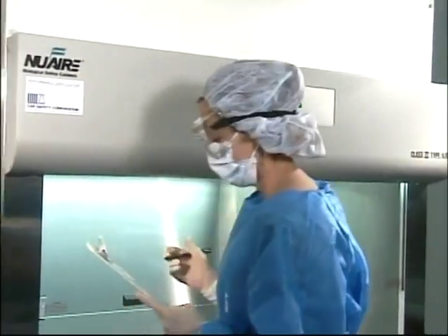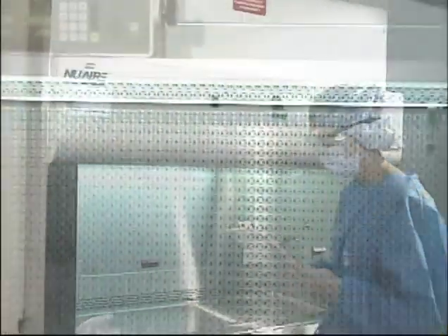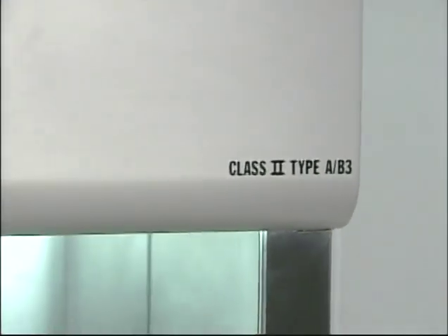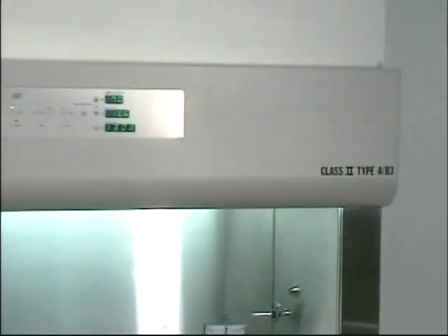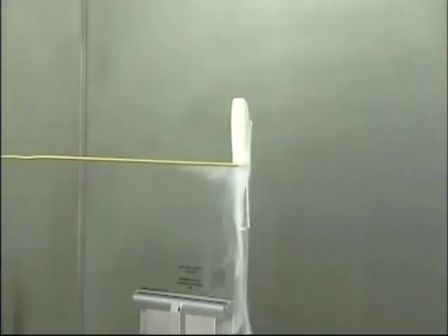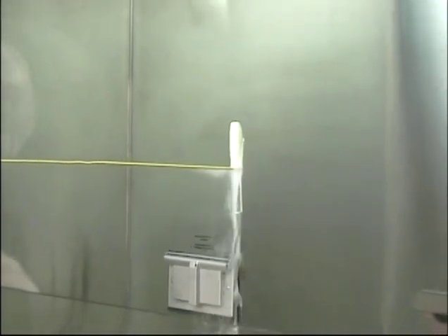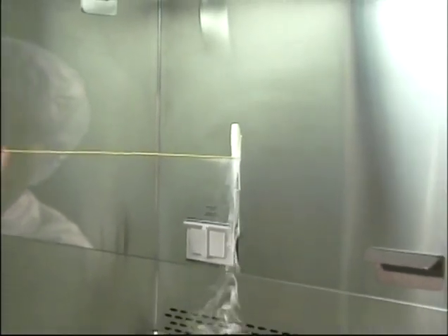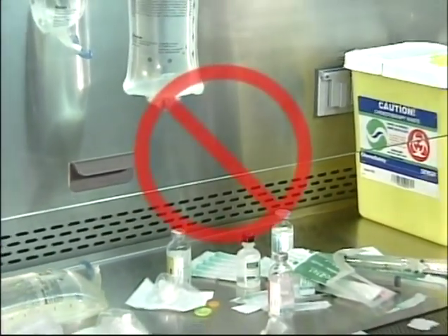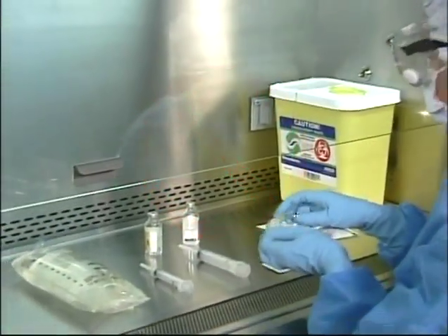All sanitizing operations should be logged on the hood cleaning log. As with the LFCB, several design aspects of the BSC must be observed to prevent contamination of the personnel, product, and the environment. When arranging objects in the BSC, remember that the first air is provided from above the work surface.